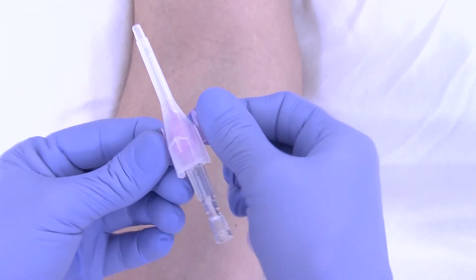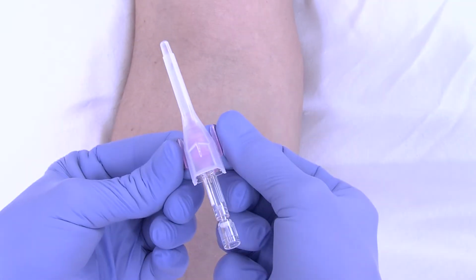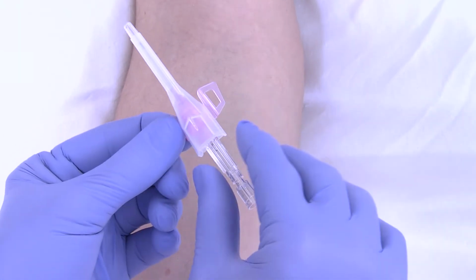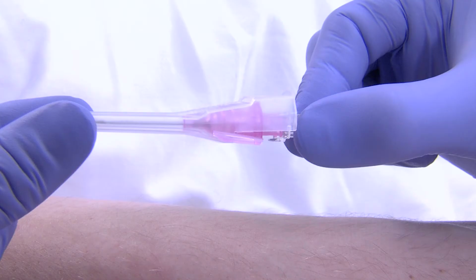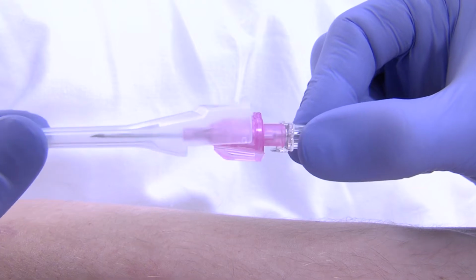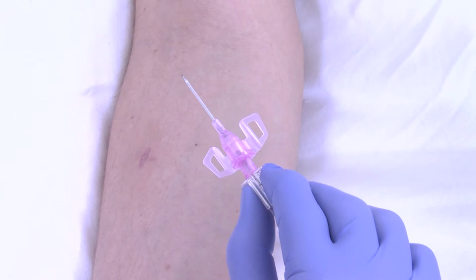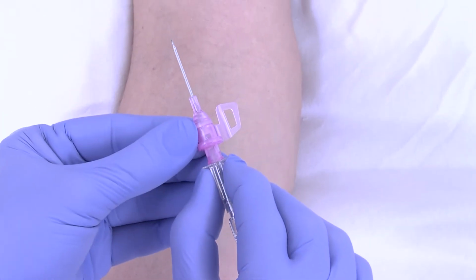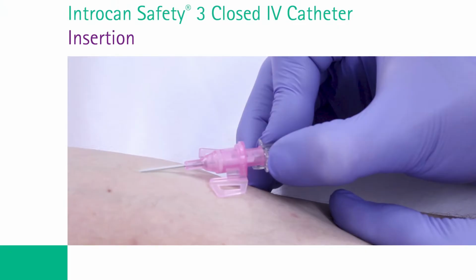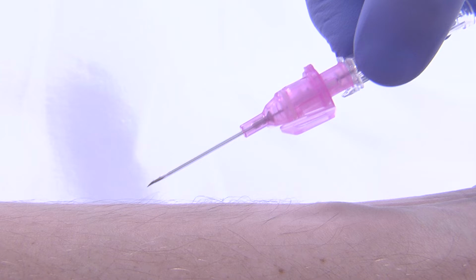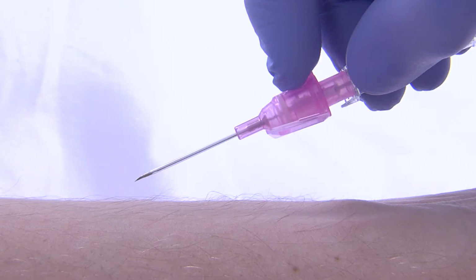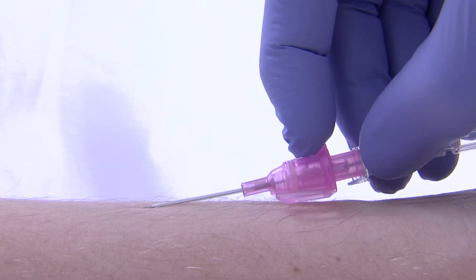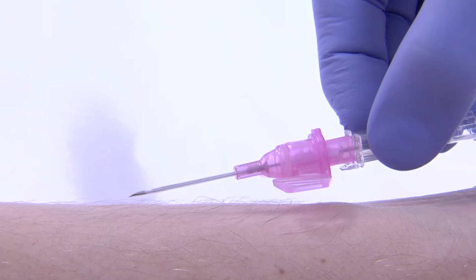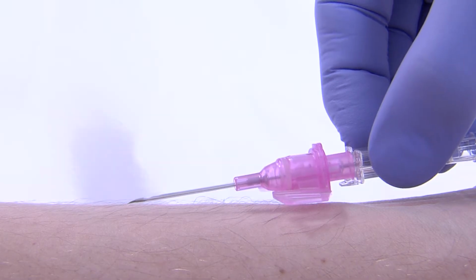Flex the stabilization platform by lowering and raising the platform and return to a horizontal position. Holding the protective guard and flashback chamber as shown, remove guard in a straight, outward motion. Confirm catheter hub is properly seated on the flashback chamber. The IntrocanSafety 3 closed IV catheter is designed to accommodate a variety of insertion techniques. Choose the grip that is most comfortable to you and allows clear visibility of blood return in the flashback chamber.